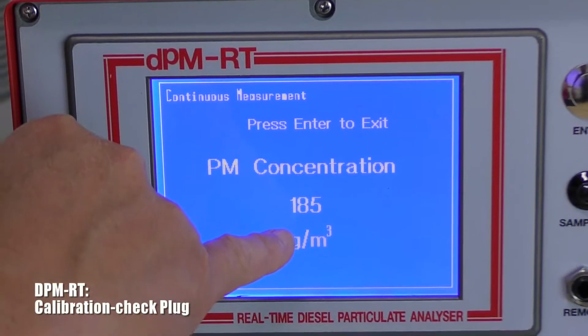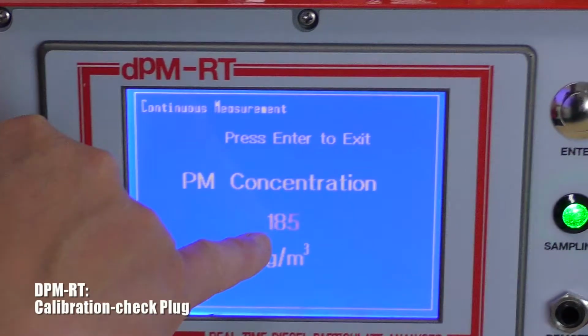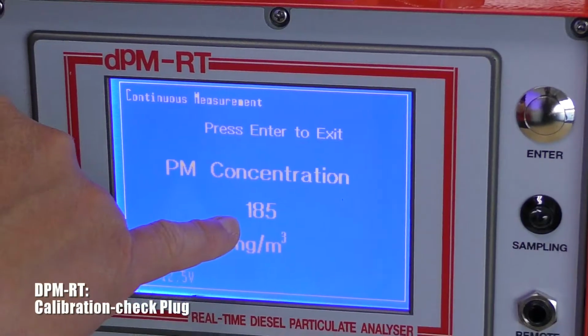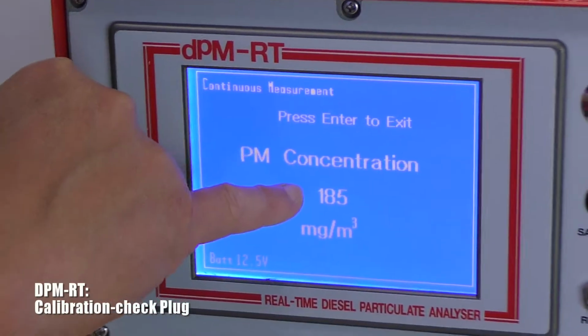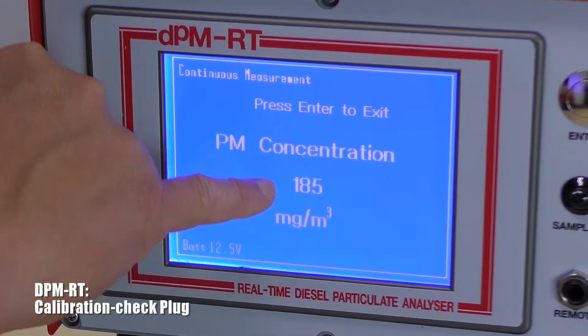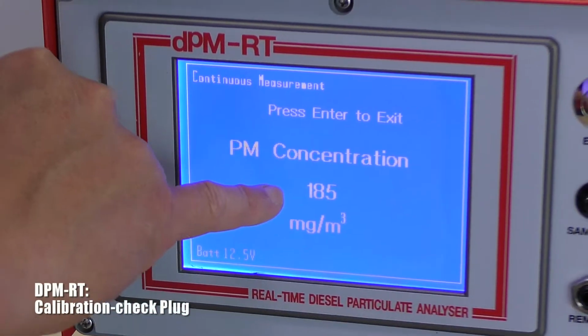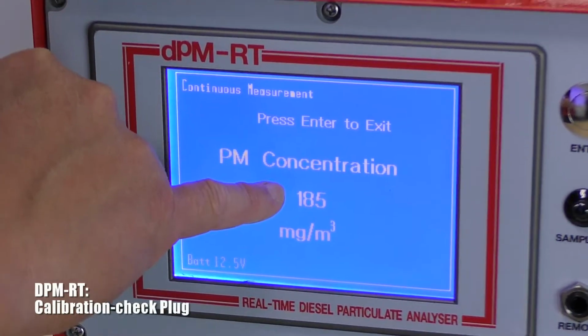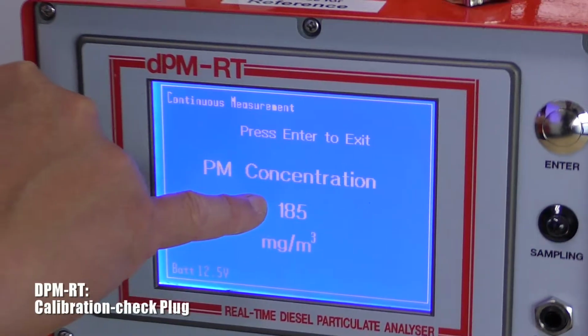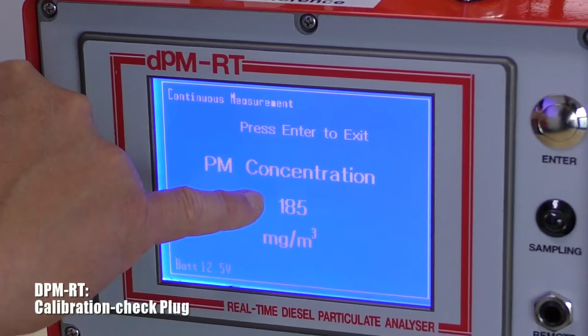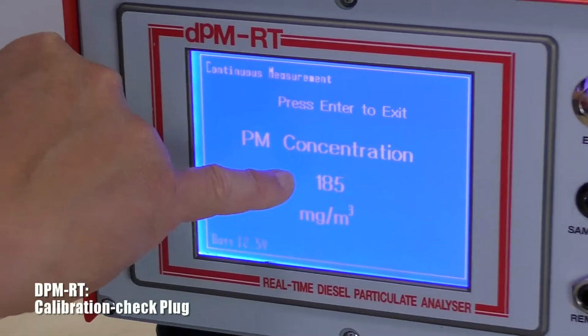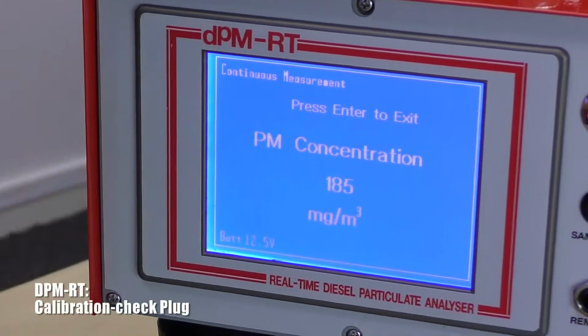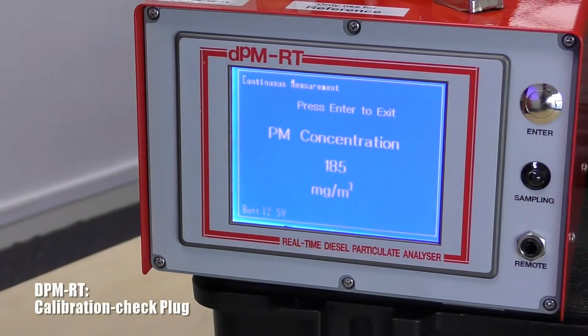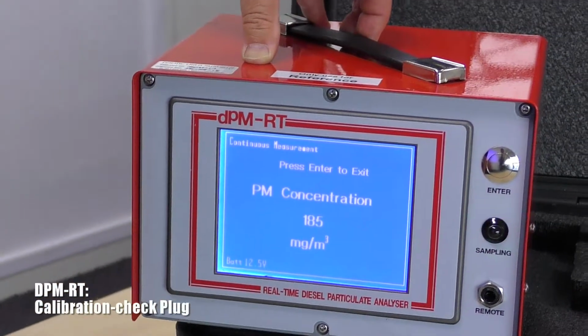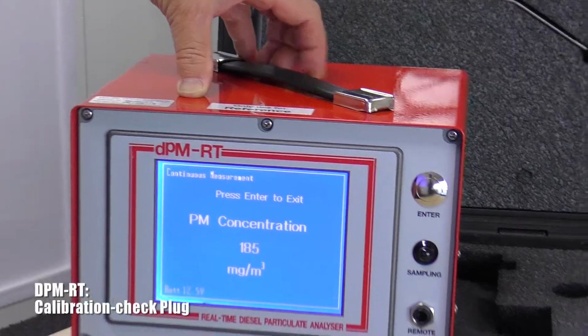The value on the calibration check plug, as a reminder, was 186, and it's being displayed on the screen as 185 milligrams per cubic metre, so it's certainly within the calibration check point range of plus or minus 5% of the value on the calibration check plug. When you're happy with that result, you can switch the instrument off.